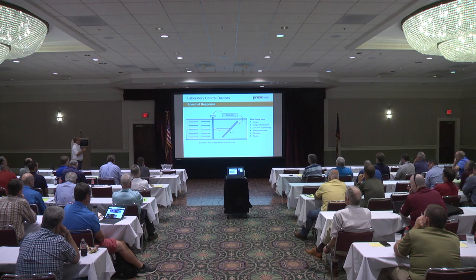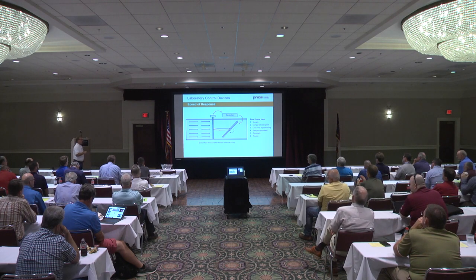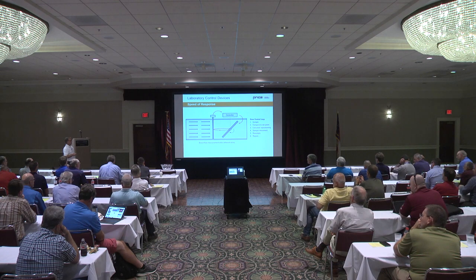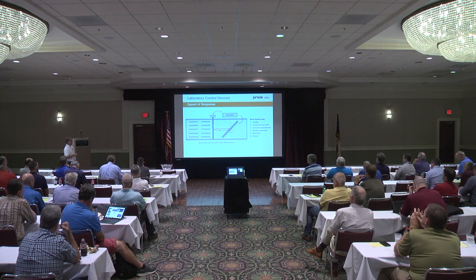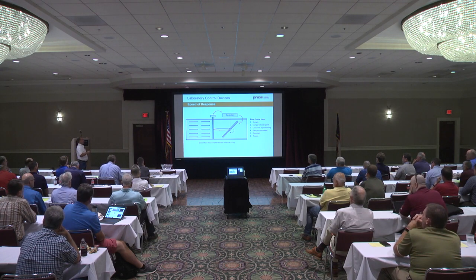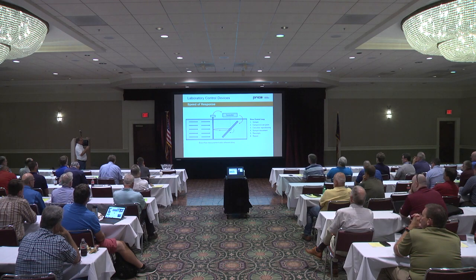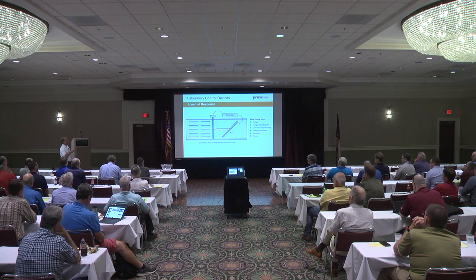Again, it's another example of airflow sensing, controller moving the damper, and speed of response. The speed of response on a device where you're measuring the airflow and adjusting the damper has got to be fairly slow, or you'll get fluctuations around your set point that you can't meet. You'll overshoot and undershoot and have to keep resampling to get it to set point. So the speed of response when you're measuring airflow has to be fairly slow so that you can let the damper react, get another reading, and then finally hit your set point.